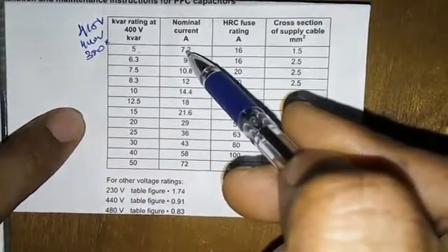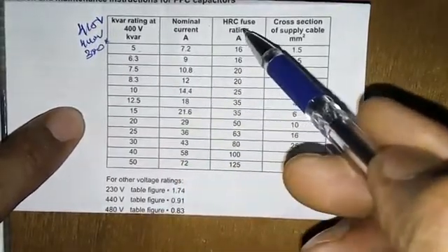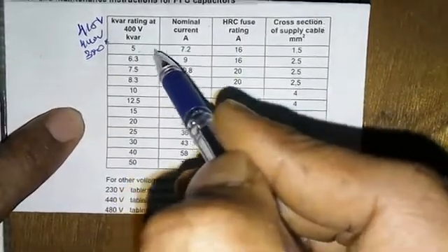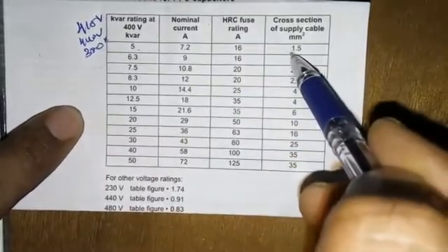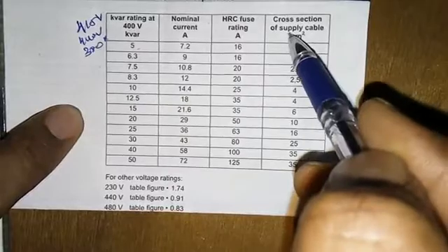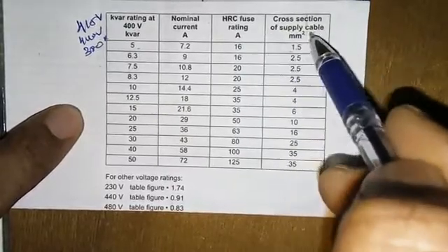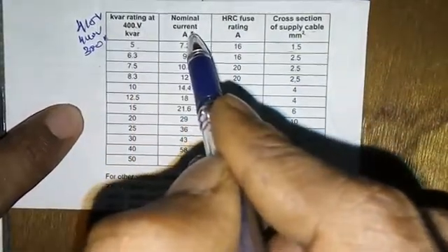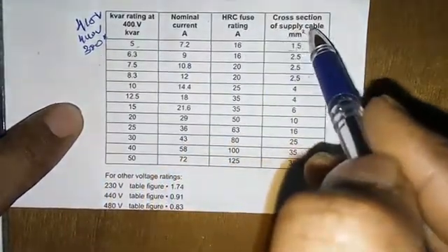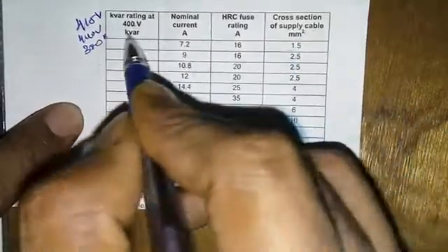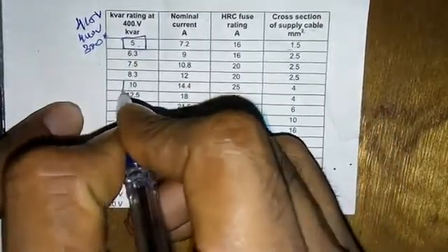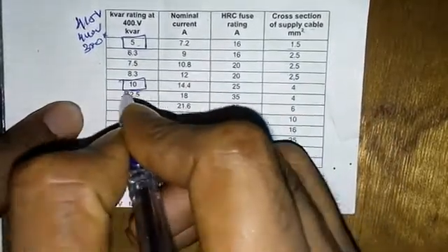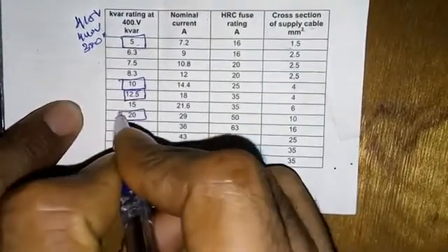The kVAR ratings are available here along with the nominal current rating. For 5 kVAR, 7.2 ampere current should be consumed, so you can choose a 16 ampere HRC fuse and 1.5 square mm cable for connecting the capacitor to the load. This is the way we choose the capacitor for capacitor bank assembling.